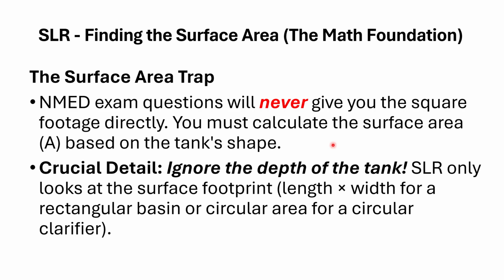Okay. One thing to remember, and this has tripped up some people, it sounds like it shouldn't, but it does. Ignore the depth of the tank. You're not interested in it. You are only looking at the surface footprint, the plan view, the view from the top looking down. So for a rectangular basin or clarifier, you're looking at length times width. For circular, you're looking at the surface area of that circle, which is pi r squared.